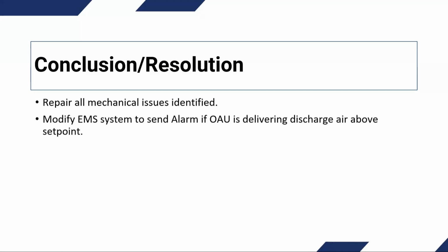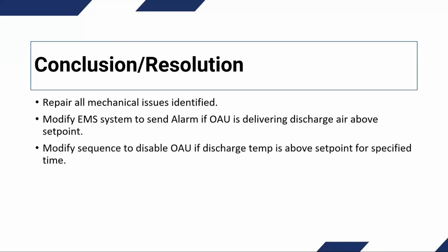We also modified the EMS system on this particular project to enable an alarm to come back to the owner if the discharge air temperature was not being met on the units, on the outside air units. So anytime the discharge air was above set point for a certain amount of time, it would send an alarm notifying them that they needed to look at it.